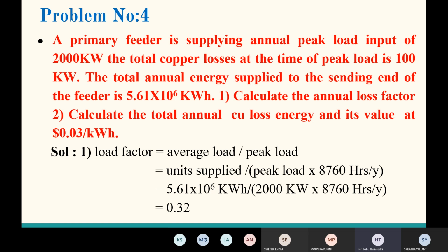You can observe in that problem they gave the peak load, right? Write down the given data. Maximum demand or peak load equals 2 megawatt. The losses at peak load, that is, power loss at peak load, equals 100 kilowatt.